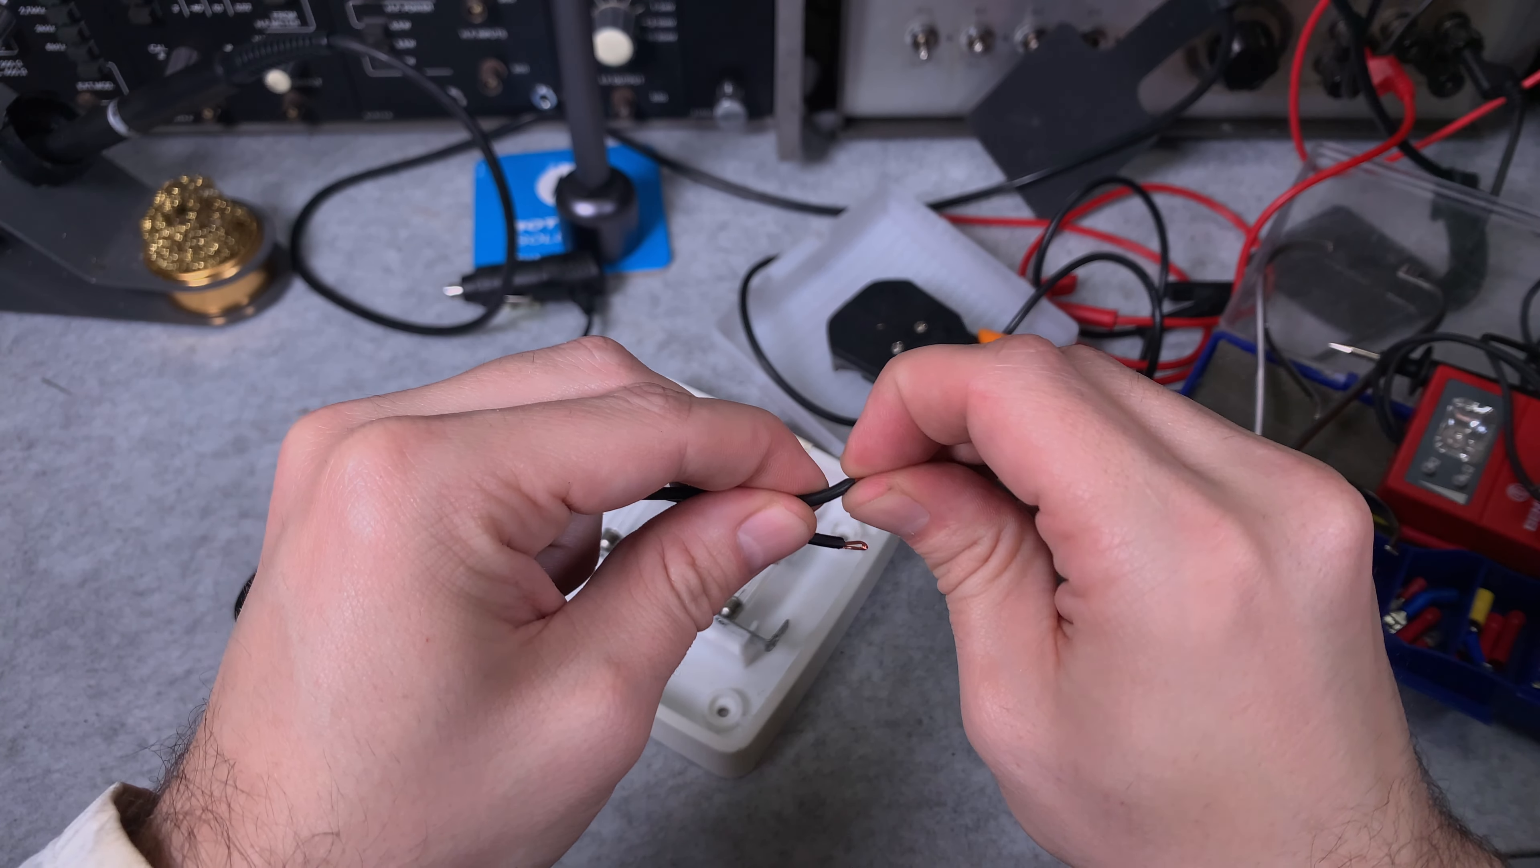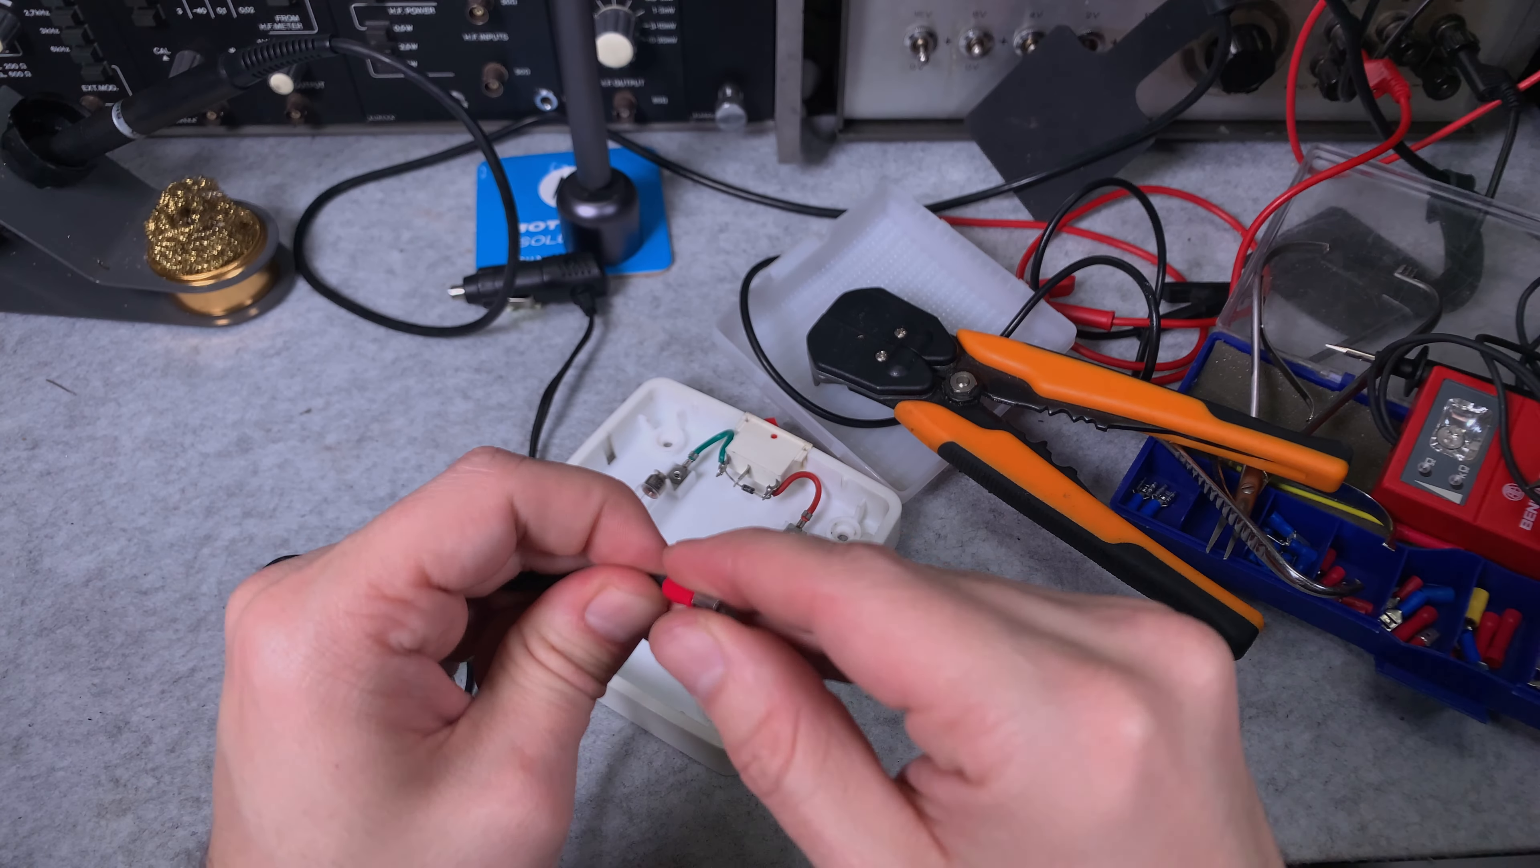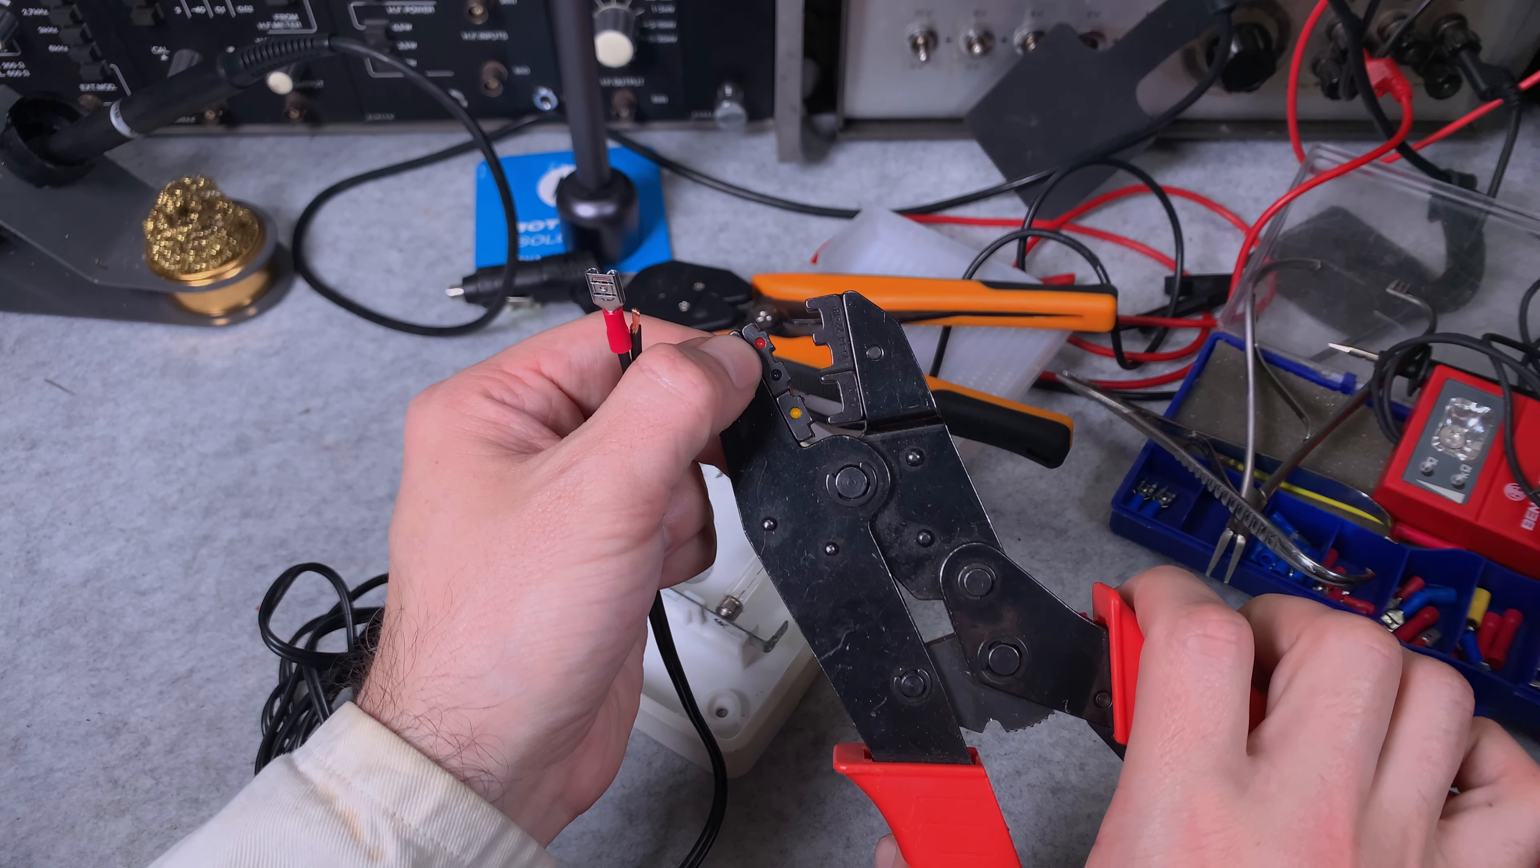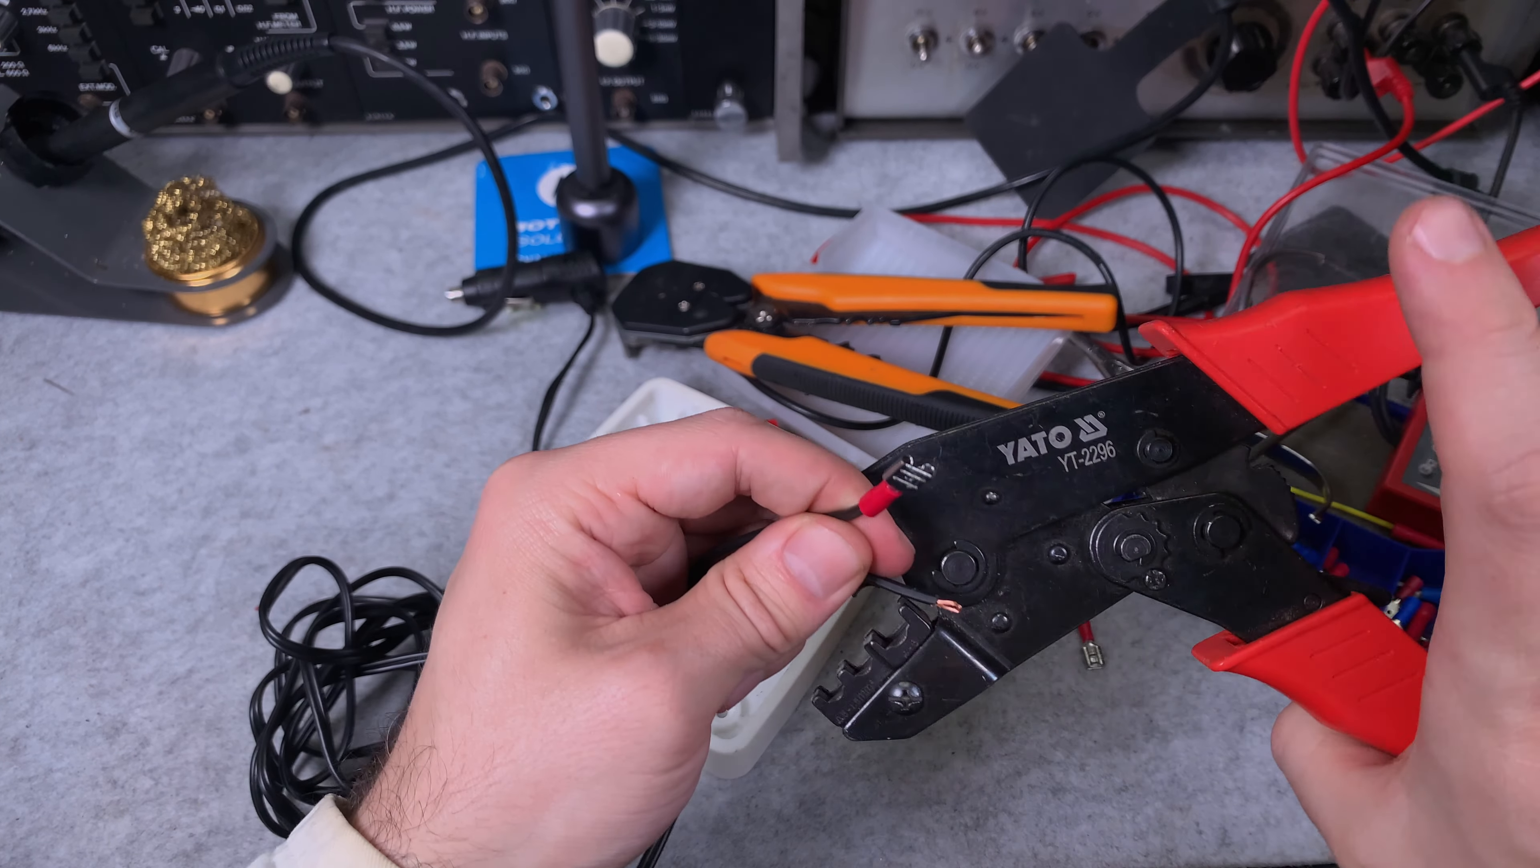So it gets more copper to create a better crimp, and I'm going to insert it. We are going to see if it nicely fits, and yes it does. Now we grab our crimper. We are going to follow the red color code, which is the smallest one.